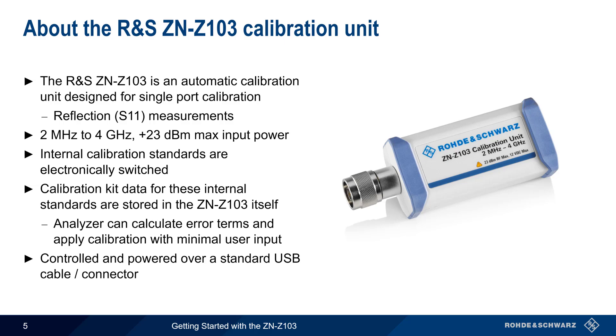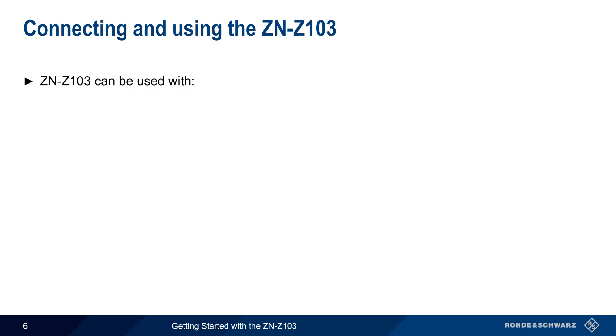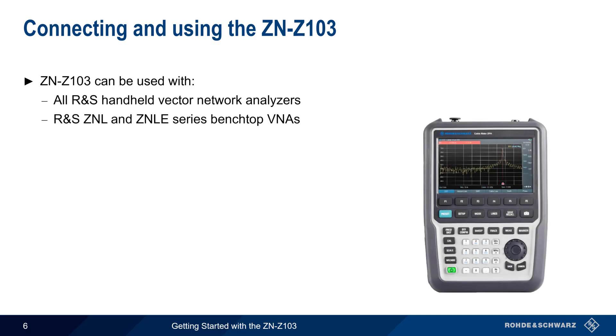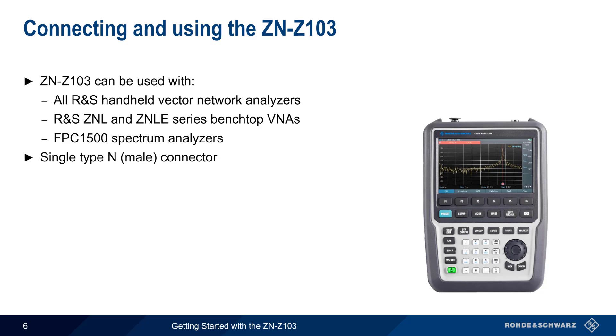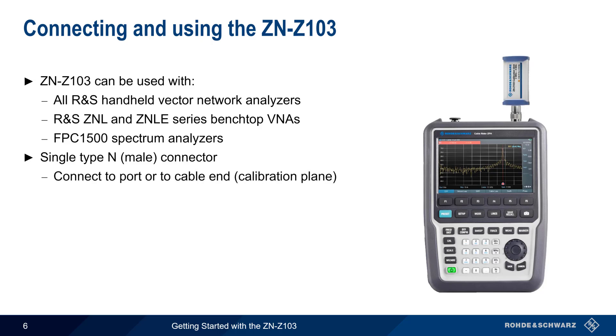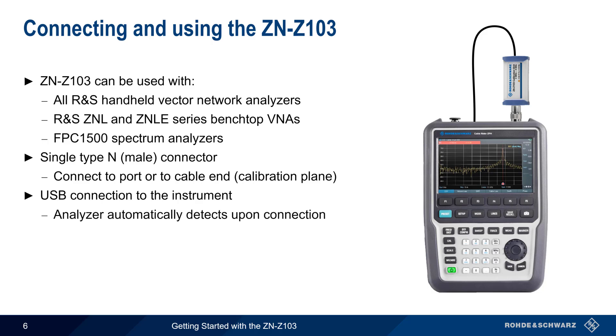The unit is controlled and powered over a standard USB cable. The ZN-Z103 can be used with all Rohde & Schwarz handheld VNAs, as well as with the ZNL and ZNLE series benchtop VNAs. It can also be used for calibrating VNA measurements made with FPC-1500 series spectrum analyzers, since these have an internal tracking generator and VNA bridge. The RF connection is a standard N-male connector that is connected either to the analyzer port itself, as shown here, or to the end of the cable or other device that represents the calibration plane. It's connected to the analyzer via USB, and the analyzer will automatically detect the ZN-Z103 upon connection.